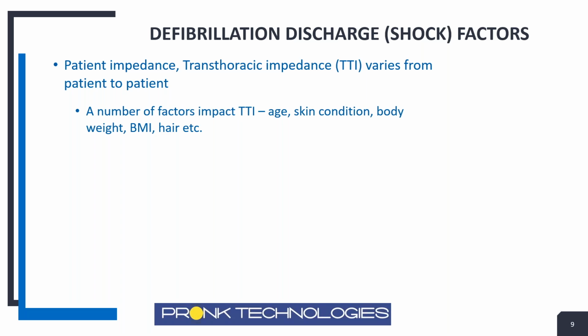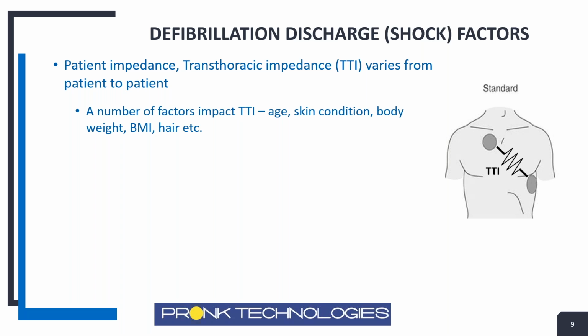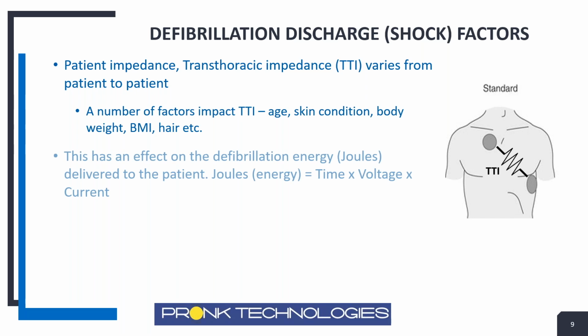And so, of course, that shock test has to be able to function across a wide range of impedances across the patient, something that's referred to as a transthoracic impedance. And it varies from patient to patient. We all don't have the same impedance across our chest. There's a number of things that can affect that impedance that the defibrillator needs to be able to compensate for: the age, the condition, body mass, weight, hair. And so the defibrillator has to be able to fire the right amount of energy under all these variables. So it needs to work properly.